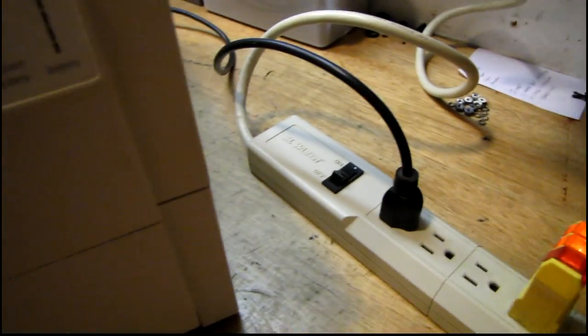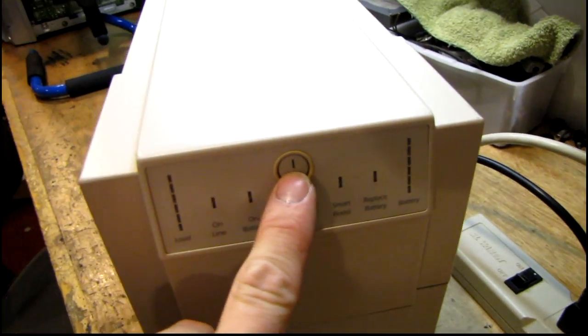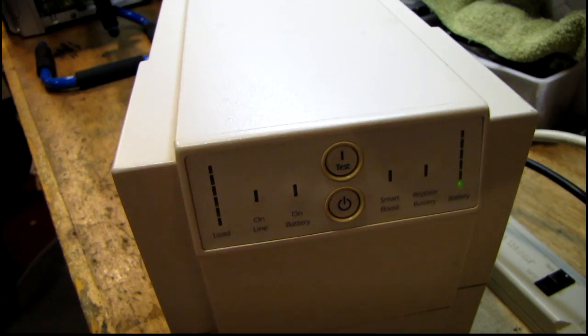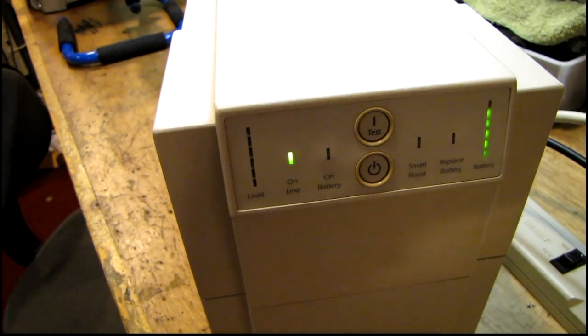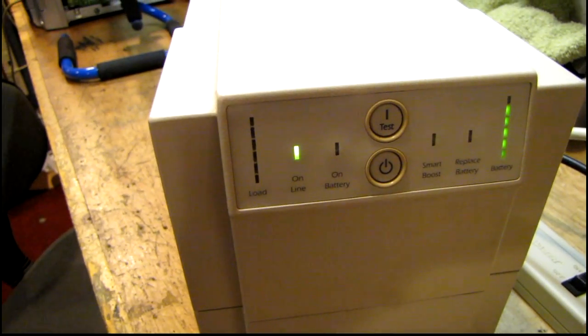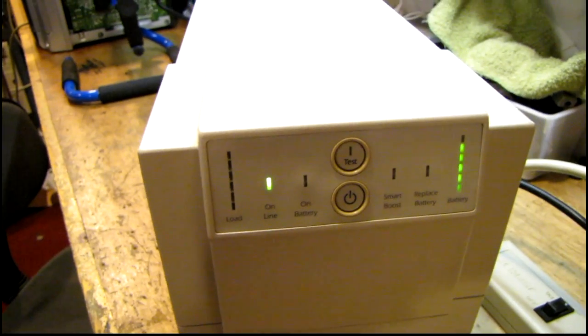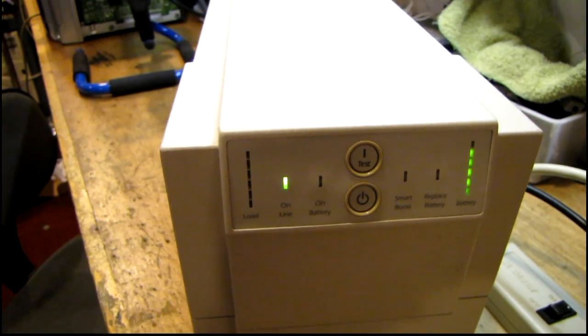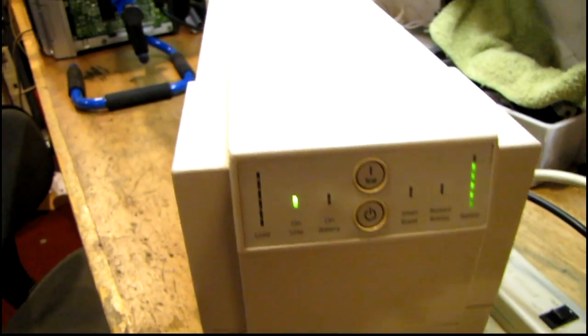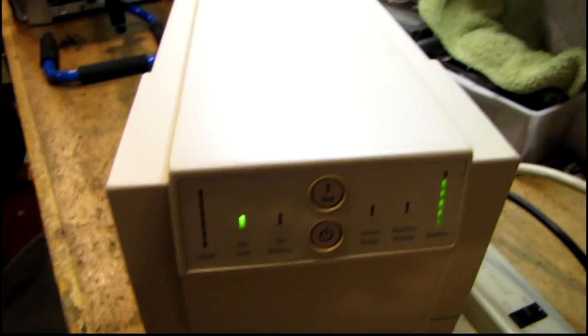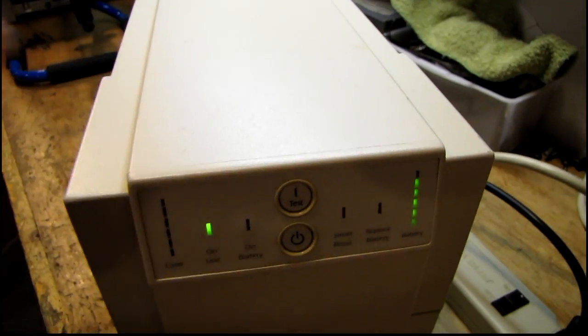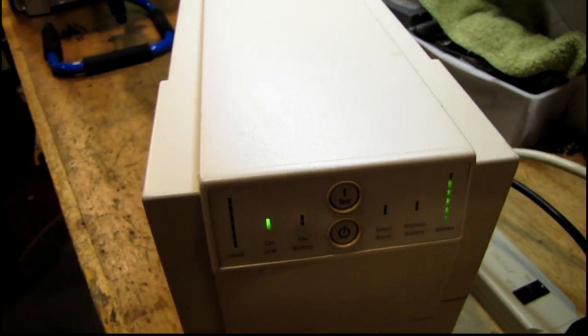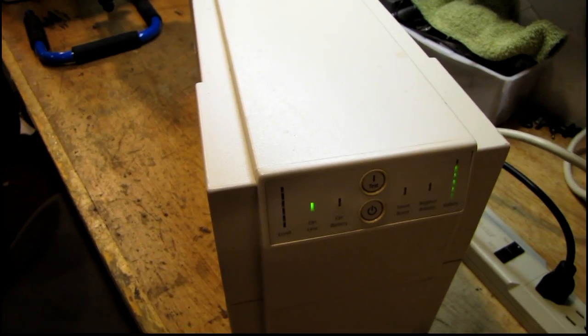The power strip is turned on, so now we'll turn on the UPS. Let it go through its self-test. And the batteries are going to be a little low from being on the shelf. You have to let them charge up until the fan shuts off in the unit and the gauge is full. And I'll show you the next step.